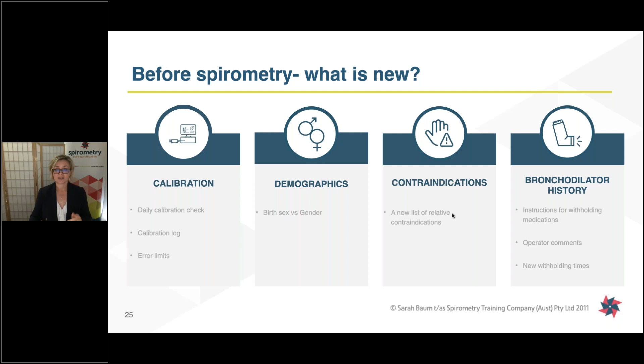For calibration, if you are using a spirometer that uses a pre-calibrated mouthpiece, typically these were marketed as not requiring calibration every day, and it was quite an attractive sales pitch because it was a spirometer that then didn't need a calibration syringe to use it. However, that's no longer the case. It is now a requirement if you're going to meet these international standards to do a daily check of the calibration. So you're checking that those pre-calibrated mouthpieces are still in range. And if anyone is using an ultrasonic spirometer, you'll know it's not possible to calibrate that. But again, a check of that calibration or that it's working within its limits is required. And that's on every day of use.